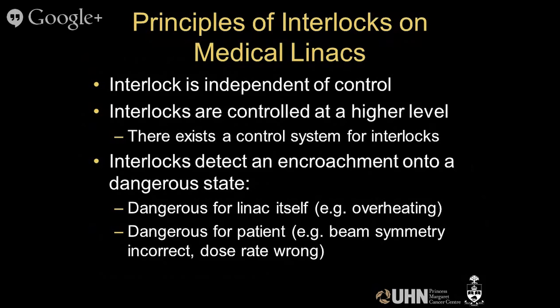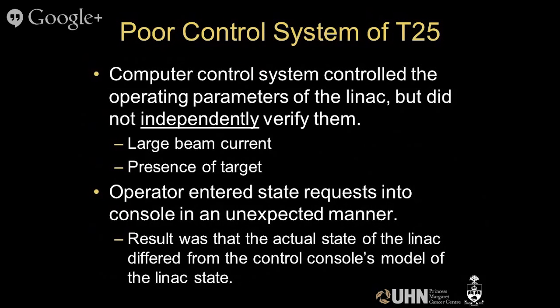And so the dangerous state can be either dangerous for the patient, as was the case with the Therac 25, or dangerous for the machine itself. So the Therac 25 had, I think we pretty much recognize now, a poor control system. The computer control system controlled the operating parameters of the Linac, but it did not independently verify them. So in this case, there was a large beam current, and the safety of the machine depended on the presence of a target to intercept that beam current before it went onto the patient. And so there's no independent checks of that.